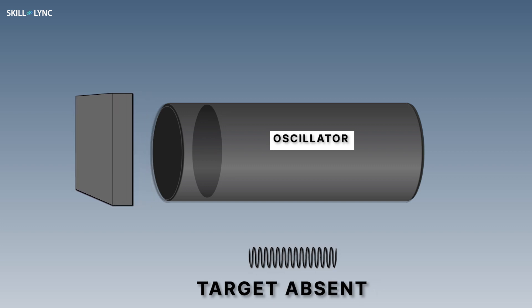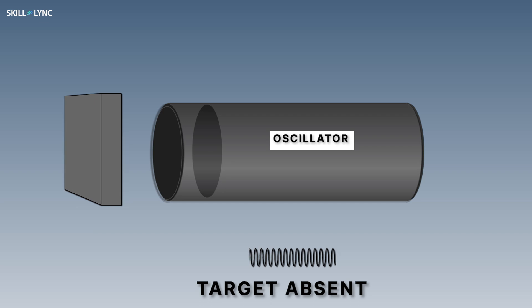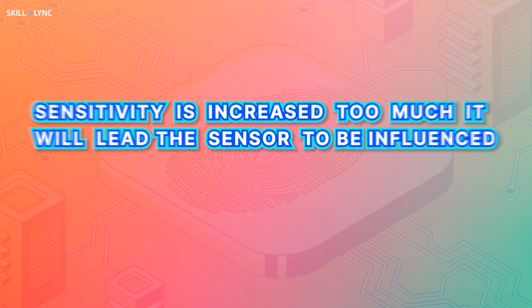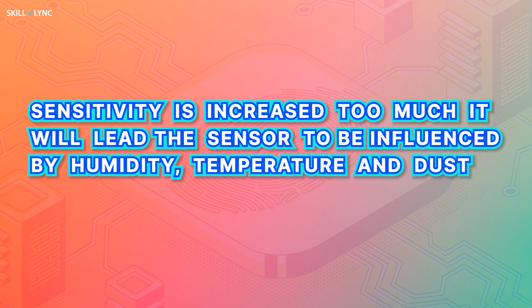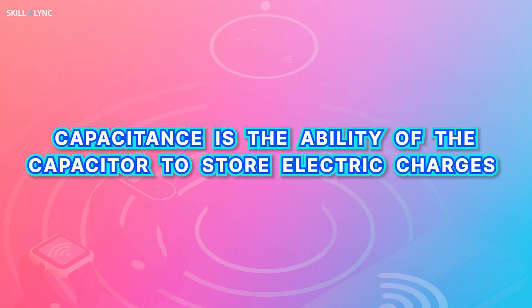This continues until it reaches a definite threshold. When the target plate is removed, the oscillator regains its original waveform. The sensitivity level of capacitance sensors can be adjusted, but if the sensitivity is increased too much, it will lead the sensor to be influenced by humidity, temperature, and dust.